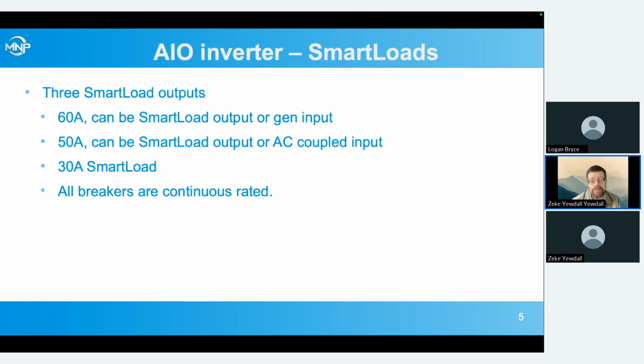We have 3 smart load outputs. Two of these can be outputs or inputs. The 60 amp is either a smart load output or a generator input. The 50 amp can be either a smart load output or our AC coupled PV array input. And then we also have a 30 amp smart load. So depending on your needs, you could have up to 3 smart loads or be using a generator and AC coupled PV array, plus still have a smart load left.